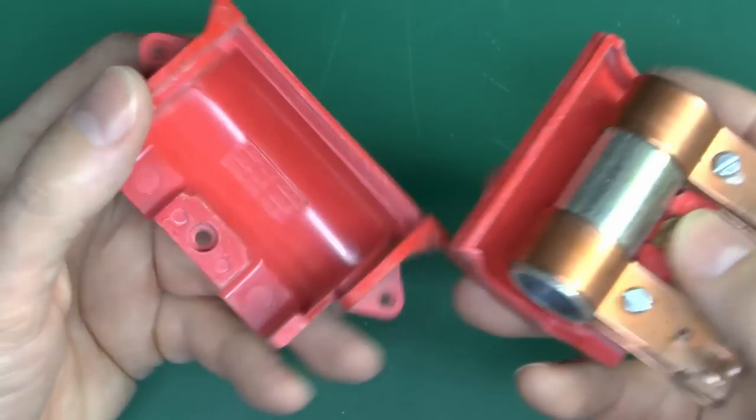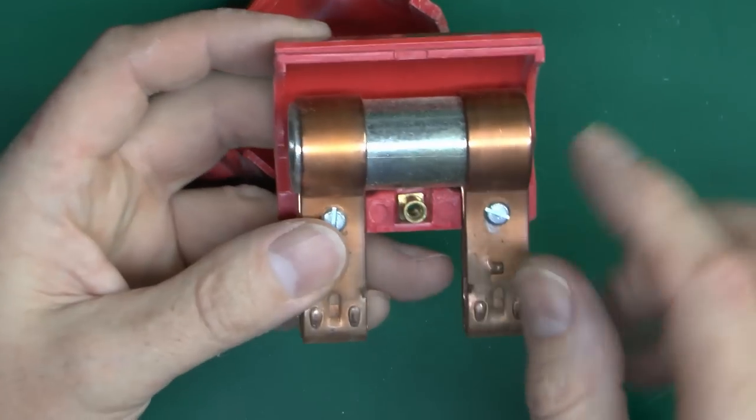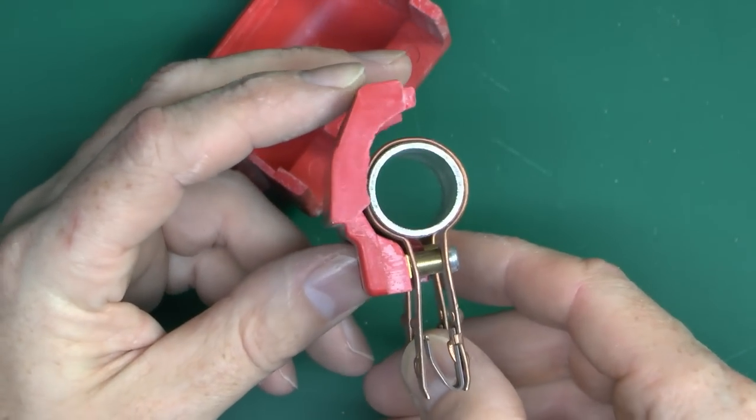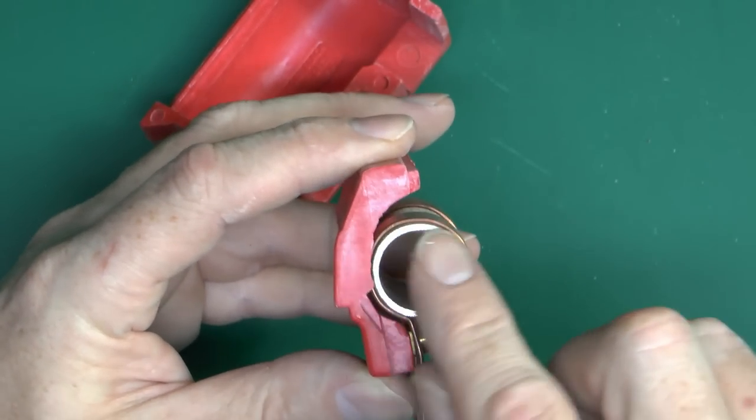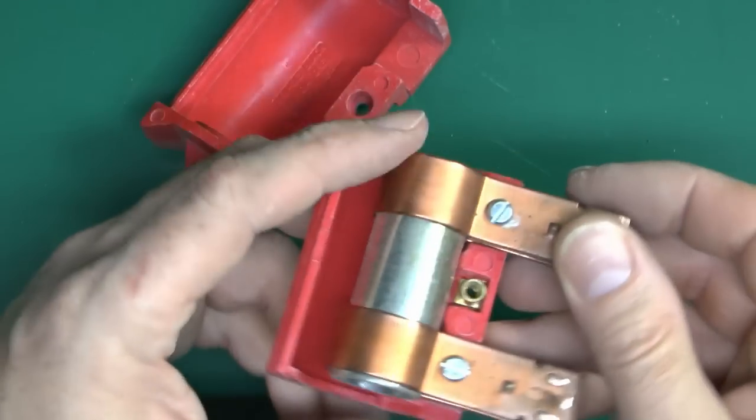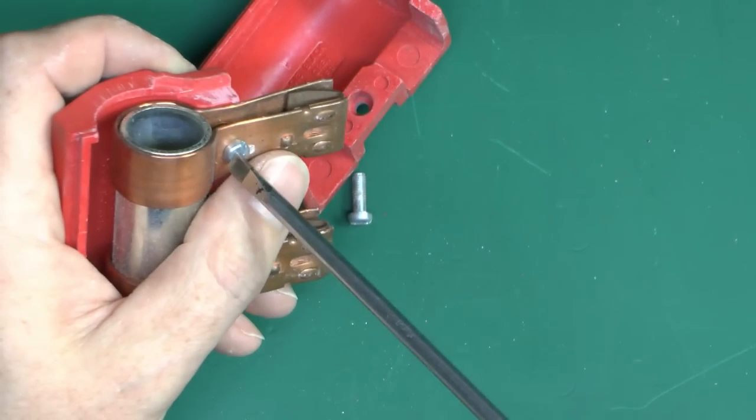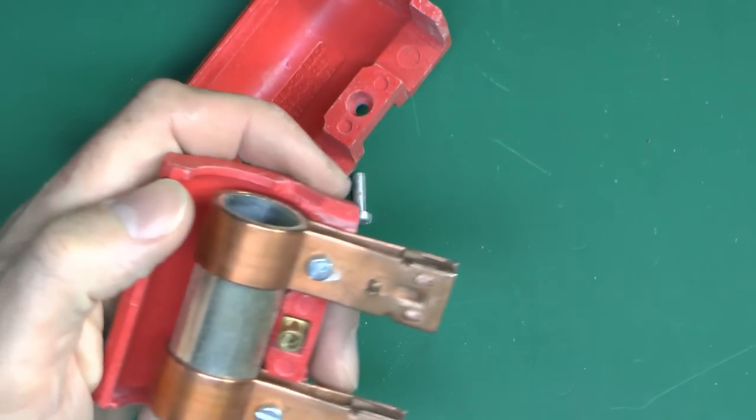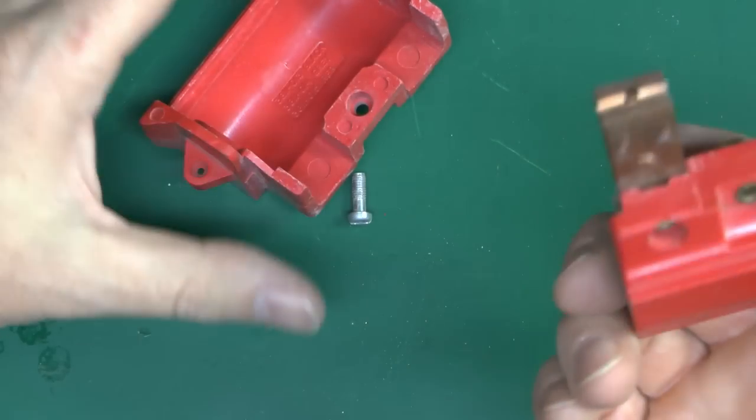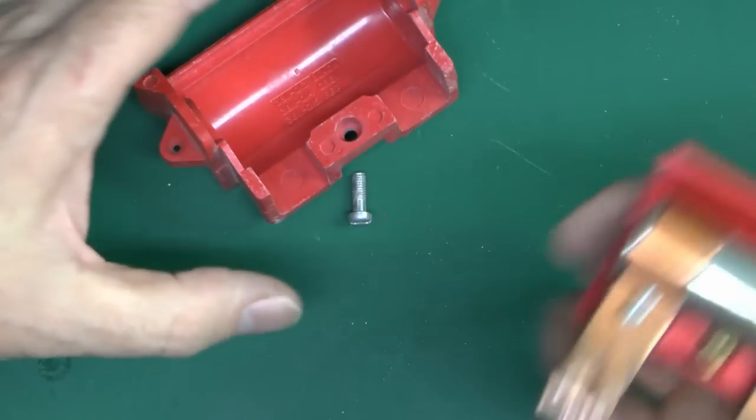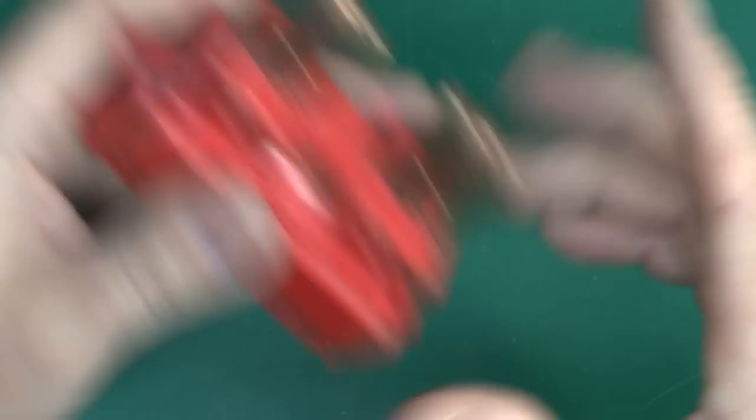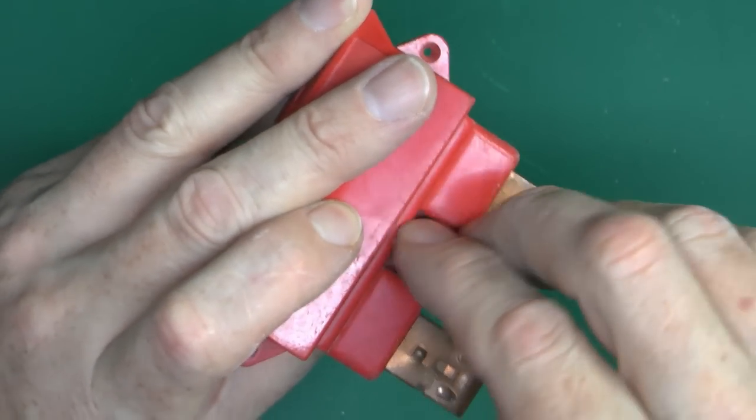So let's take this apart and see what's in here. Same construction again, the two halves there with the big overlap and all the rest. As you can see here, this is just a solid metallic link there, this piece of fairly thick walled metal tubing. So same idea of construction, and you could take that out if you wanted just by loosening the screws here, but it's purely providing a means of disconnection of the supply. There's no overload protection here whatsoever, hence the red colouring to indicate that it is literally just a solid link inside there.